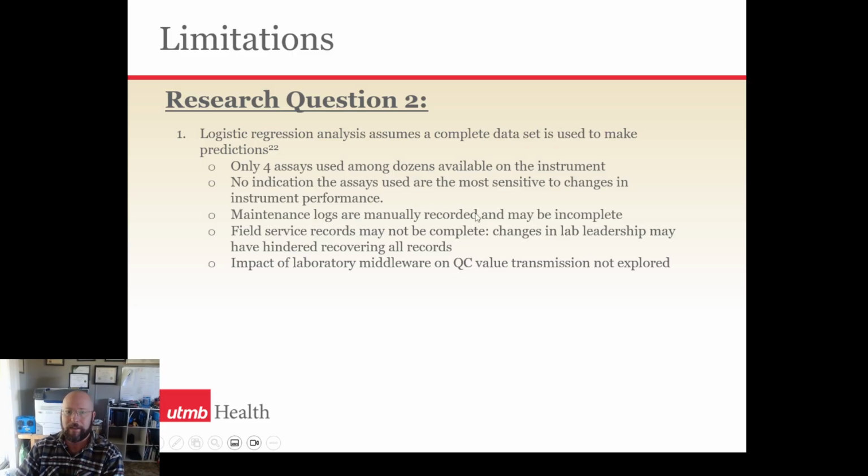Maintenance logs are manually recorded and may be incomplete. So just because somebody filled something out doesn't mean they didn't do it. Field service records, again, may not be complete. And the impact of laboratory middleware on QC value transmission wasn't explored at all. So we used Beaker for our QC results, but the laboratory uses a middleware that might block some of those results from even getting to the LIS.